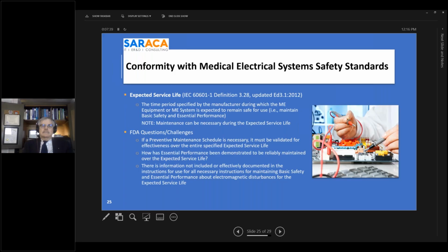Also: how has essential performance been demonstrated to be reliably maintained over the expected service life? There again, essential performance pokes up, and that really means, is it safe for its clinical use over the time frame you stated, to ensure that it provides the proper functionality and safely to specification. And the last one is: there's no information included or effectively documented in the instructions for use for maintaining basic safety and essential performance with regard to electromagnetic disturbances over the expected service life. That is a mouthful. How do you keep the product safe, basic safety and EP, when it's undergoing electromagnetic disturbances in the environment of intended use over those 10 years?